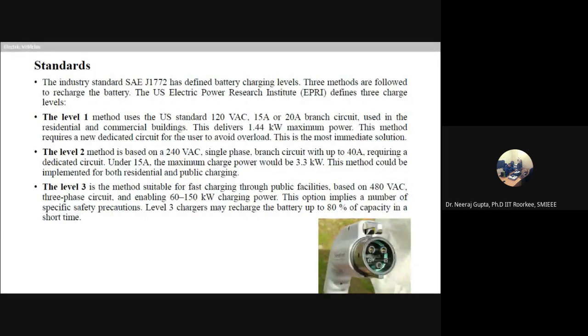This method is based on the 240 volt AC single phase branch circuit with up to 40 ampere requiring a dedicated circuit. Then level 3 is suitable for fast charging through public facilities, based on 480 volt AC 3-phase circuit, enabling 60 to 150 kilowatt charging.